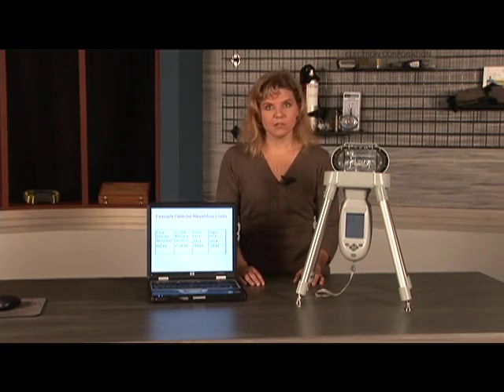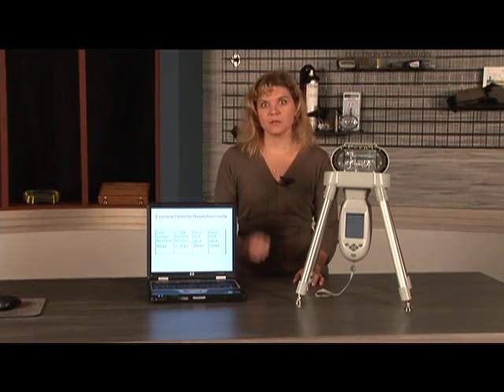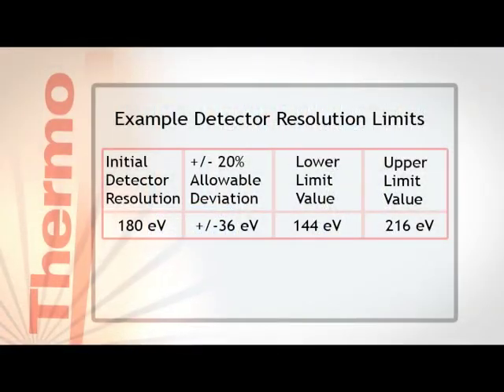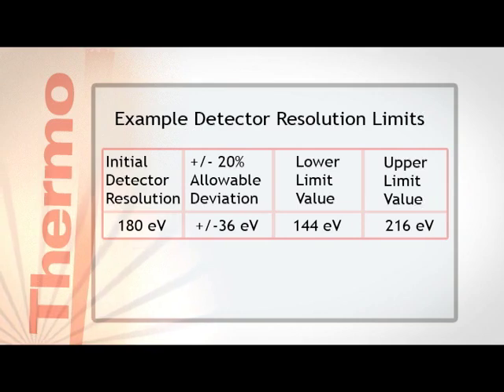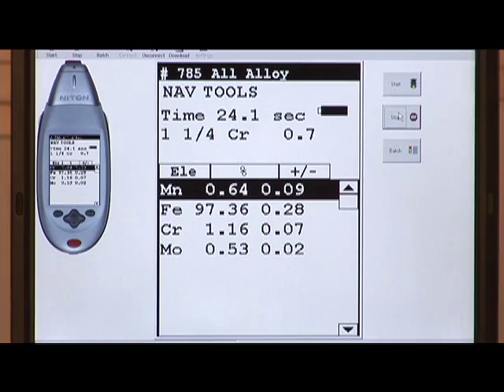Let's take a look at the values of resolution from the detector calibration that we just did. We see it is 180 eV, or electron volts, the standard unit of measurement for detector resolution. 20% of 180 is plus or minus 36. This will give you a lower limit value of 144 eV and an upper limit value of 216 eV. Any computed resolution value outside this range may indicate a problem with the detector, and you should contact your nearest Niton Analyzer service department. This screen shows the result of the remeasurement of our check sample.